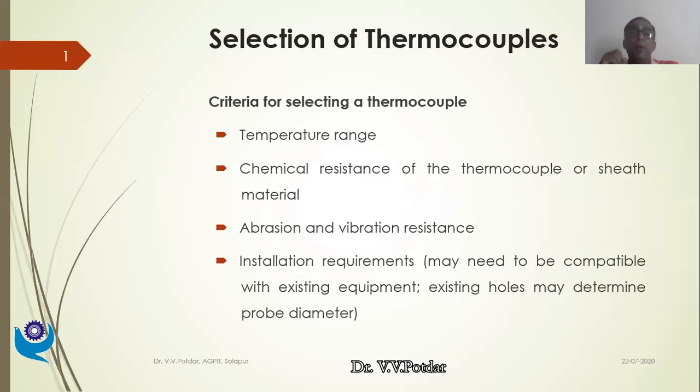Now, we are talking about the selection criteria. When I am monitoring temperature, that assembly is constantly rotating and subjected to torsional vibrations. My temperature sensing thermocouple would also be subjected to all those vibrations. Because of vibrations, the performance of my thermocouple should not get affected, or I should select such a thermocouple which can sustain those vibrations. So this is one of the important selection criteria for thermocouples.